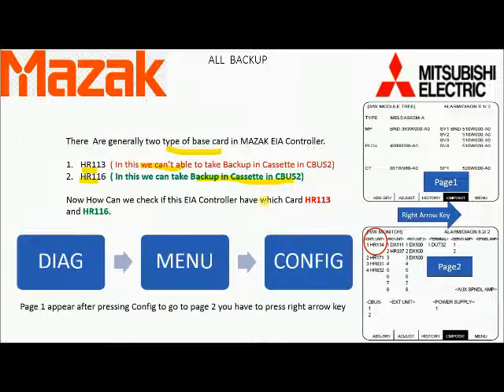First we have to know which type of card we have in this controller. Please press DIAG on the keyboard, then Menu in the soft key, then Config in the soft key. Then we will come to page 1. For going to page 2, which is the hardware page, press the right arrow key, then check the red circle — you can find the card name there: HR 113, HR 116, or HR 114.